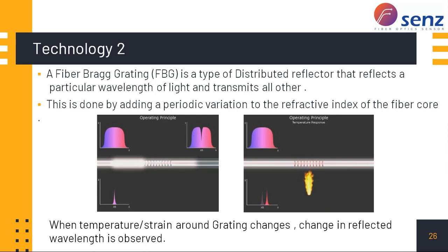So we will get multiple wavelengths and multiple outputs on the input side itself, and the shift in the wavelengths of multiple reflections would give us the temperature at each of these points. So this particular technology is used to give temperature sensing on fiber Bragg grating. A unique technology. Not many products are available based on this technology, and we can have on one fiber maximum up to 20 gratings can be written.